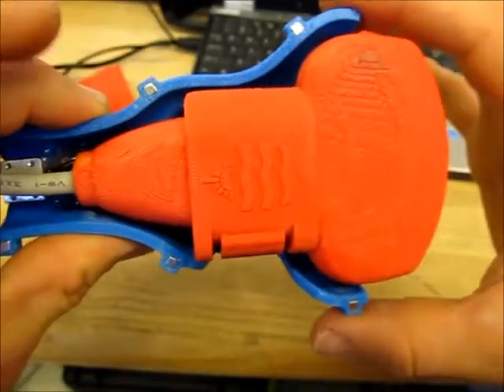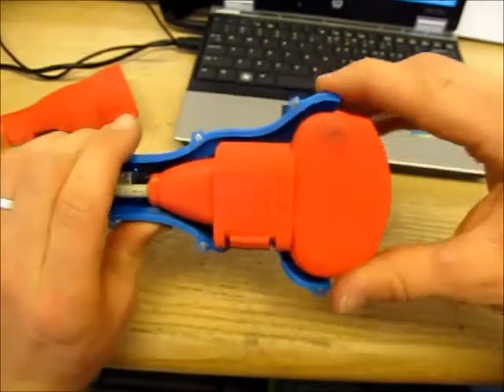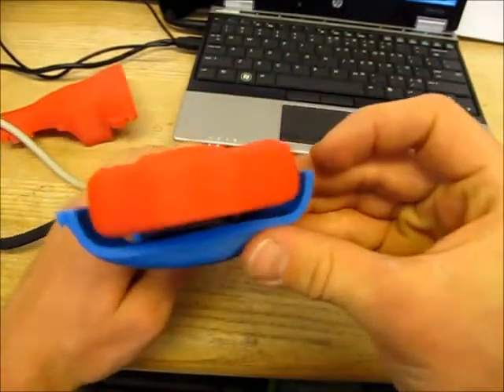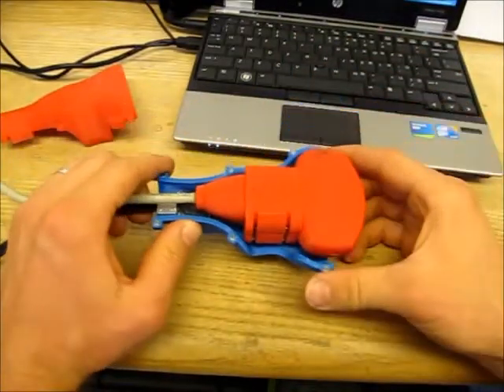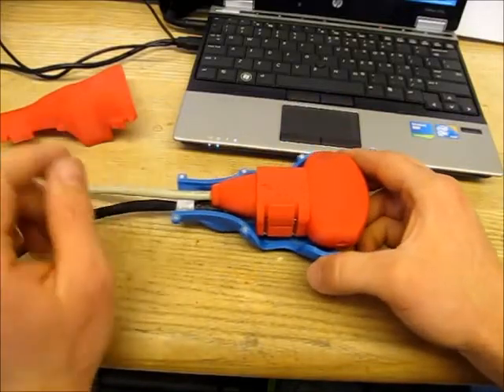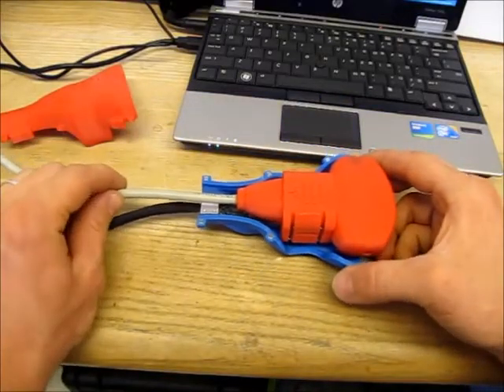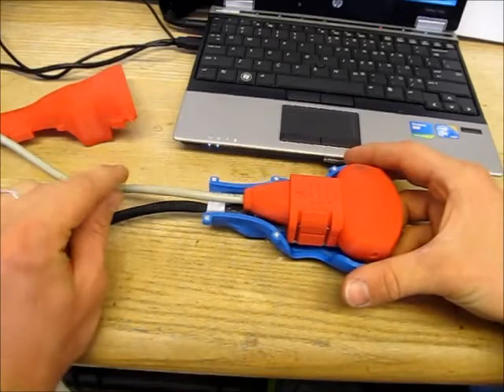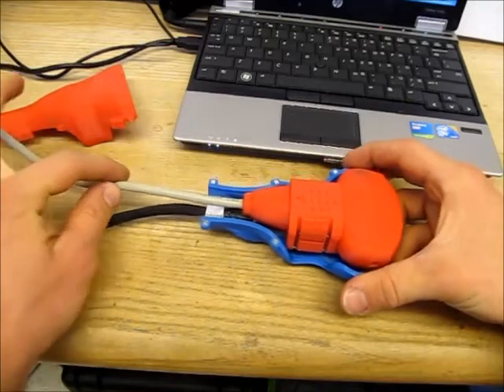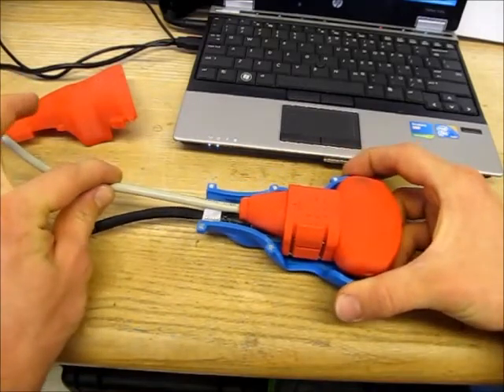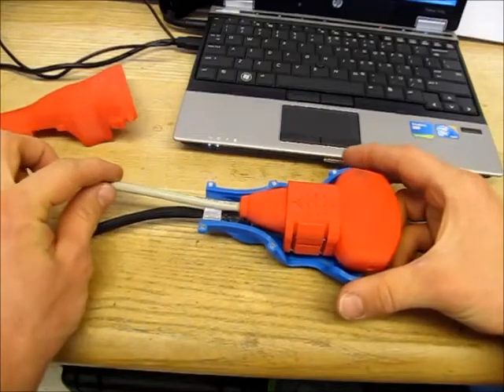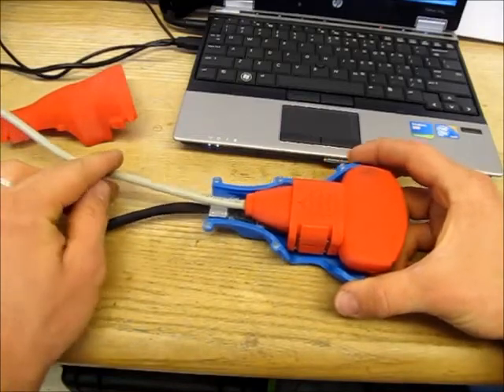So after you've locked it, you want to take a look and make sure that the probe is centered properly. Looks like we've done a good job. So the next thing we want to do is we want to strain relieve the ultrasound cable here. And the reason we want to strain relieve it is because we don't want any tension that's applied to this ultrasound cable to show up as measured contact force.